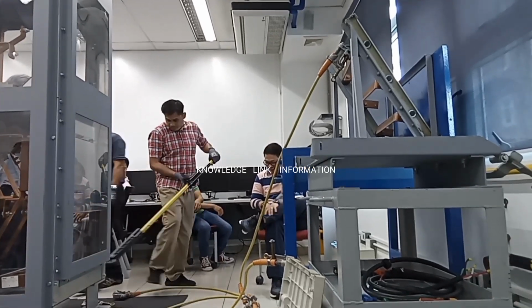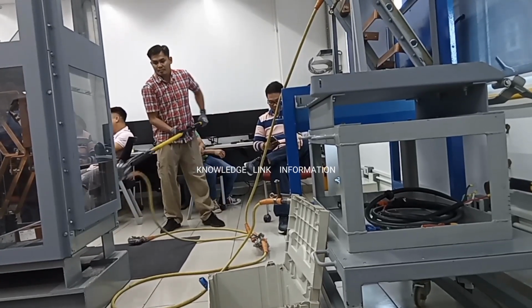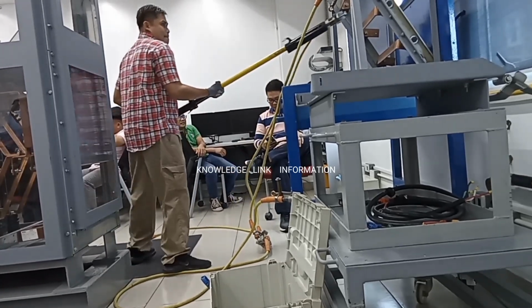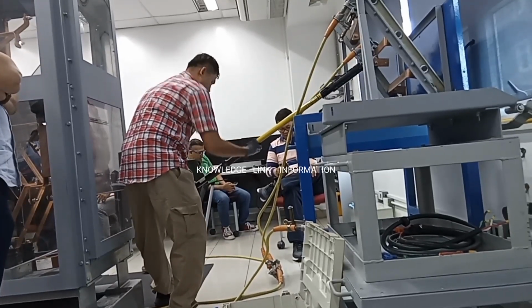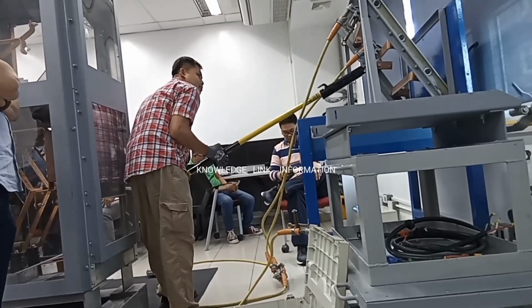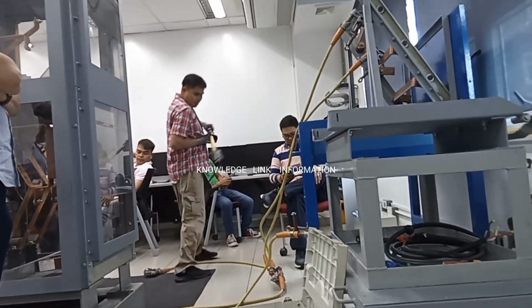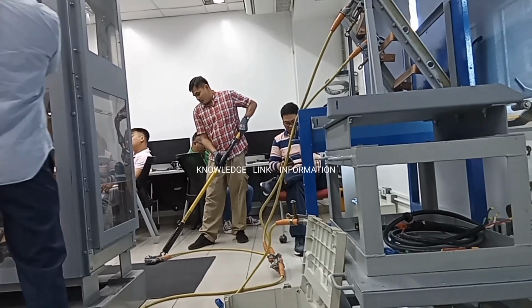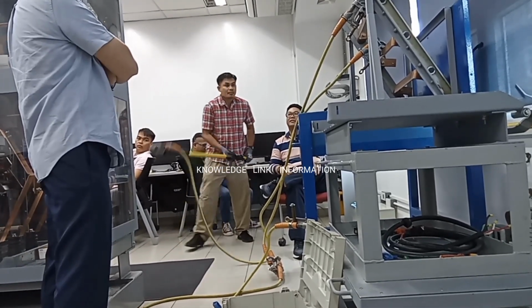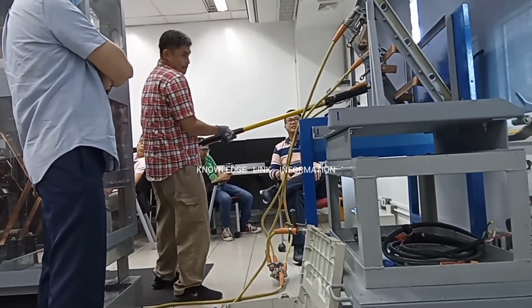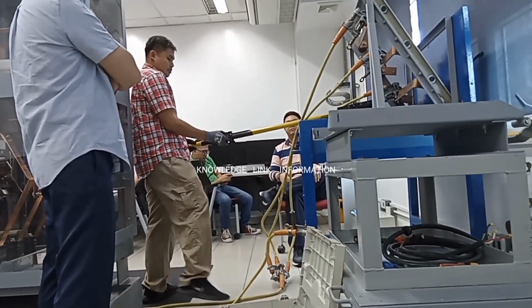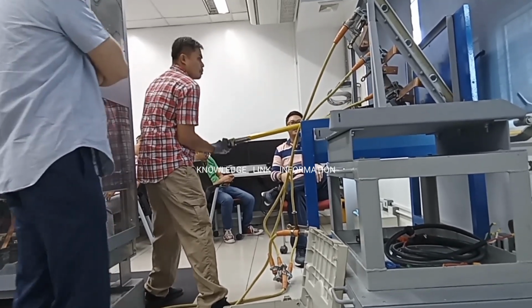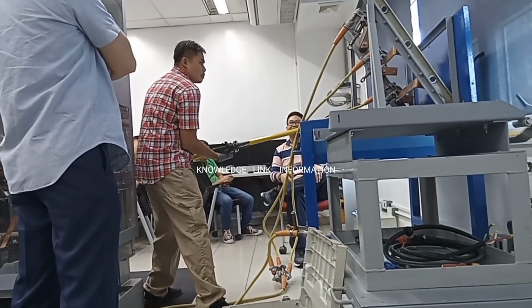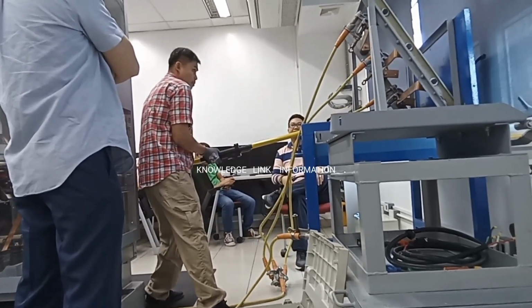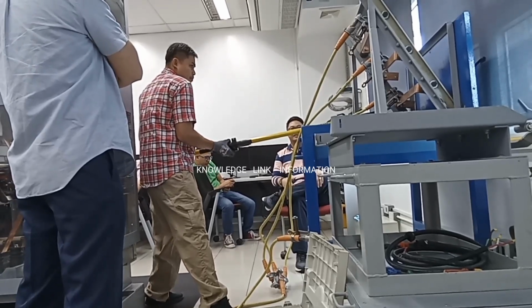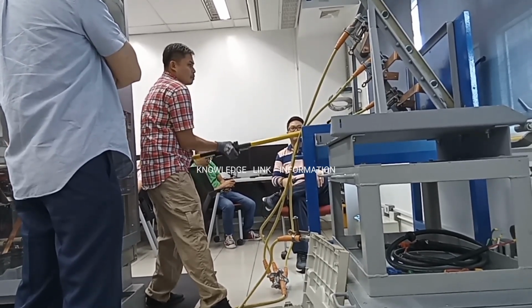Number 16. Pick up the second phase connection clamp, and connect it to the next phase of the bus bar. Avoid letting the cable leads twist and become damaged. Number 17. Pick up the third phase connection clamp, and connect it to the last remaining phase of the bus bar. Take note that using a hand for voltage testing, and using a hand for inserting ground clamps, are not acceptable in working on any high-voltage electrical system. We must always use the proper approved equipment for high-voltage systems.